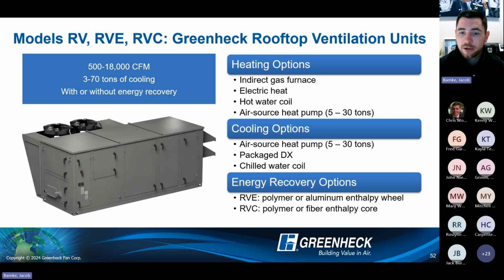So on the bottom right there, you see all the energy recovery options. The RVE is with our enthalpy wheel, and that's going to be polymer or aluminum wheels. RVC is going to be polymer or fiber enthalpy core. So everything is a total enthalpy device, wheels and cores. As far as heating options go, we do have indirect gas. We can do SCR controlled electric heat, hot water coils, and then the air source heat pump currently goes from 5 to 30 tons. So not the full product breadth, but as we get to this electrification movement and we get the refrigerant transitioned over, you will start to see some expanded tonnage ranges there as well. Cooling options besides the air source heat pump, package DX, and chill water coil.